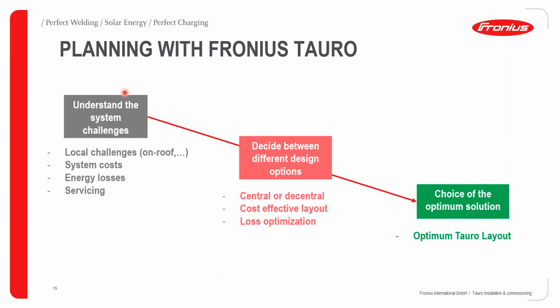So the Tauro has quite a number of advantages, and we can look at all these in a different webinar, whereby you can minimize the energy losses that you can experience over a period of, let's say, 10 years, 15 years, or 20 years, and comparatively look at what that means compared to similar inverters available in the market. Also, something else that you would need to understand as far as system challenges are concerned is the ease of servicing your products or the inverters. So the Tauro has a very unique service concept, and this will be addressed much later, and you're going to see how easy it is to service the Tauro series of inverters.